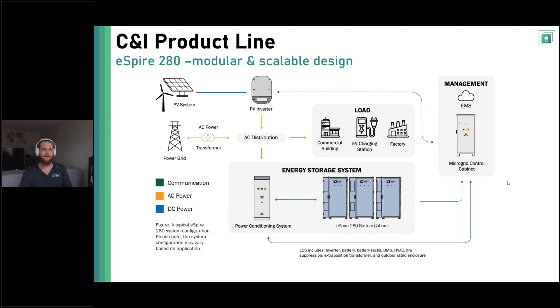Now, I want to show you guys a project that we installed up in Northern California. This is in Eureka, California. And just a quick note, this shows a 125 kW 233 kilowatt hour system. Long story short, with the UL 1741 SA and SB requirements coming down in California, we had to upgrade our inverter to be SB compliant. And as a result, to match that new voltage range for that new inverter, we needed to add a battery module to our eSpire 233 system to make it the eSpire 280 system. So just keep that in mind. This is kind of an older iteration of the eSpire, but still the same cabinet, just adding an additional battery module with an upgraded inverter and some consolidated equipment.